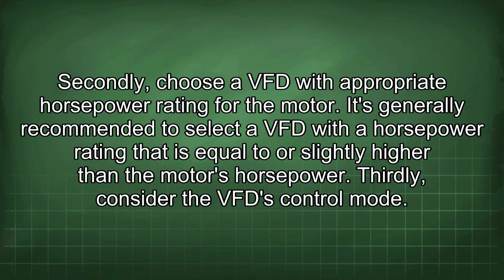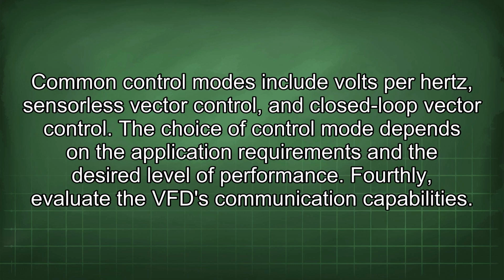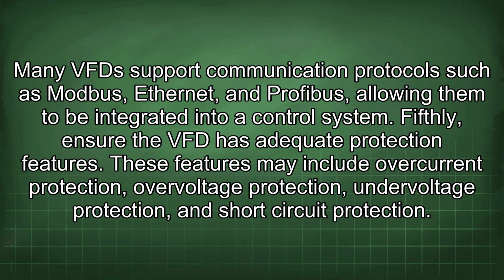motor's horsepower. Thirdly, consider the VFD control mode. Common control modes include volts per hertz, sensorless vector control, and closed-loop vector control. The choice of control mode depends on the application requirements and the desired level of performance. Fourthly, evaluate the VFD communication capabilities. Many VFDs support communication protocols such as Modbus, Ethernet, and Profibus, allowing them to be integrated into a control system.